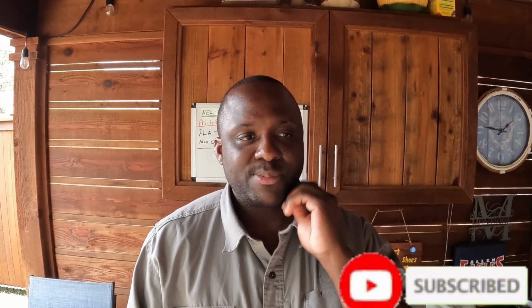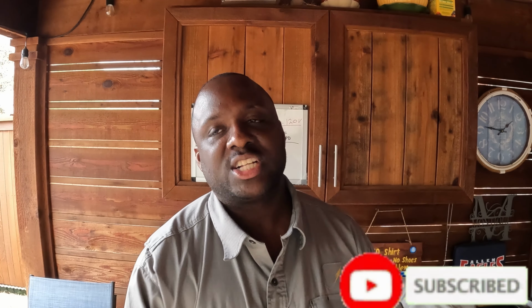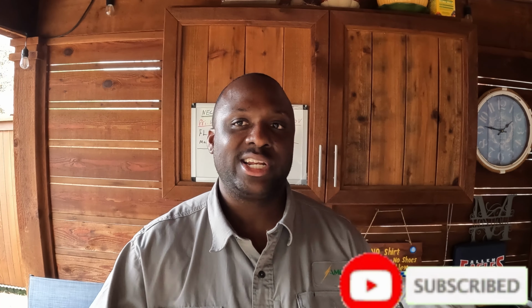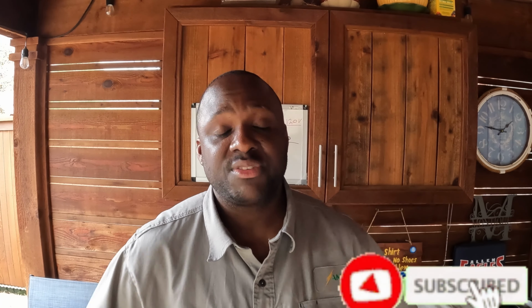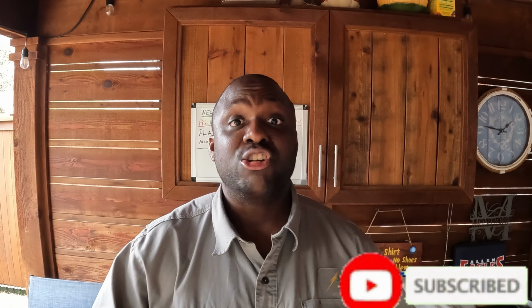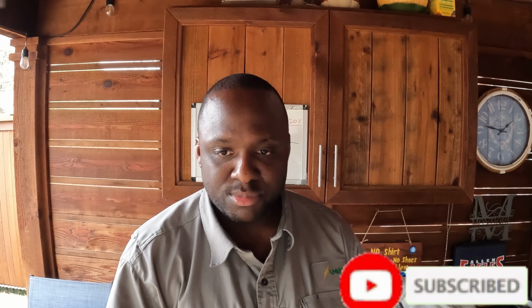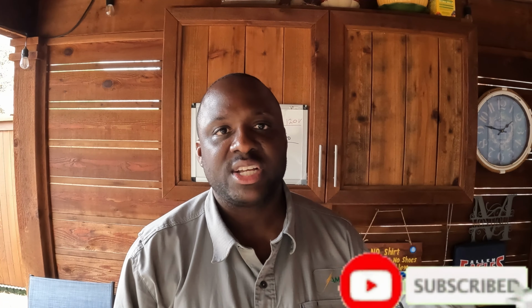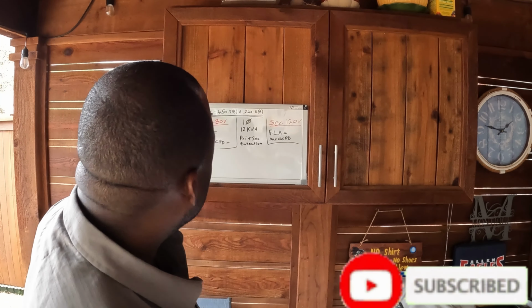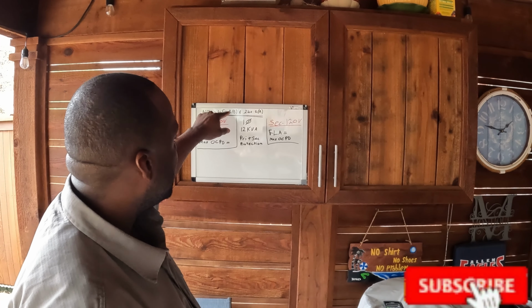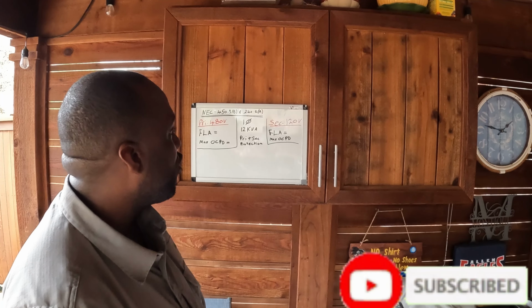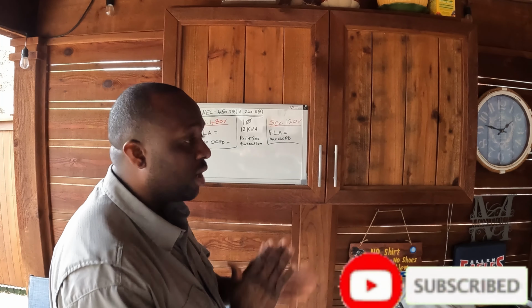The typical way a lot of people do it is they go look on the transformer, see how many amps the transformer pulls, then they look for the wire, then they get their overcurrent protective device. But today I'm gonna show you guys the right way to get the full load amps, and the minimum and maximum overcurrent protective device, using the NEC codebook. We're gonna look at article 450.3(B) and 240.6(A). Those are the two articles we're gonna look at.